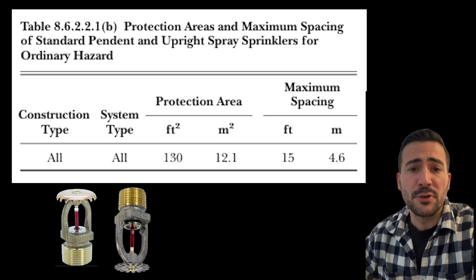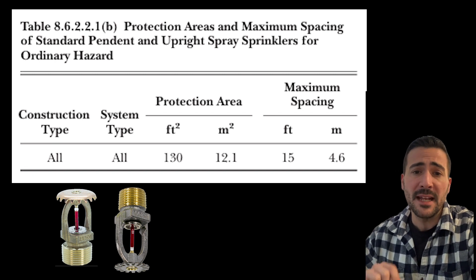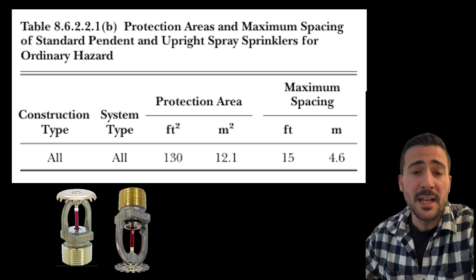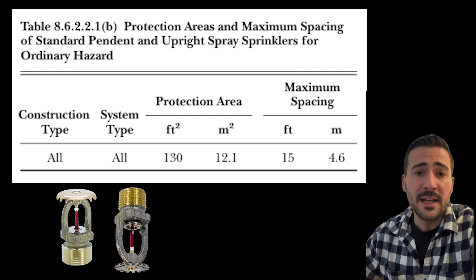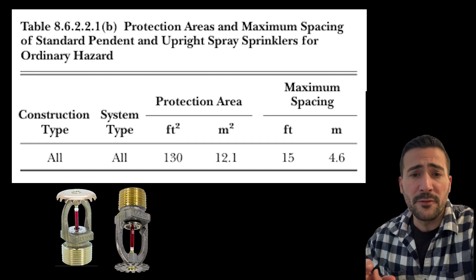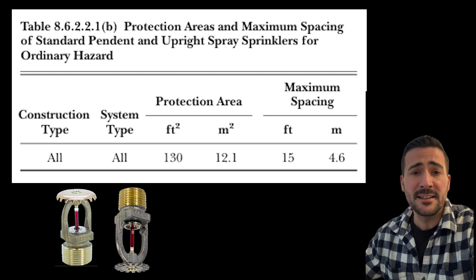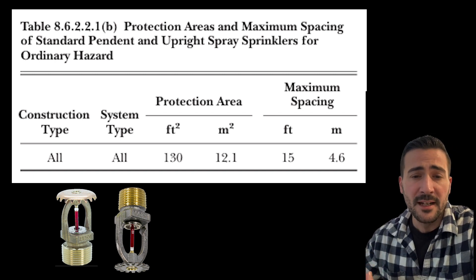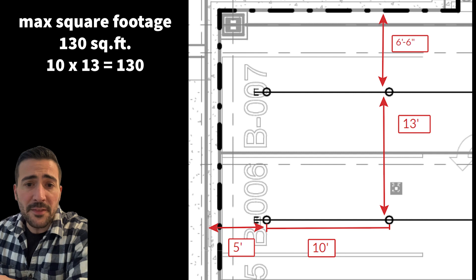Let's start off by going over our maximum protection area of coverage. NFPA 13 made tables for each style head that can be used in ordinary hazard occupancy. These tables give us our maximum square footage and our max distancing for heads. Let's start off by going over the most commonly used head: the standard spray upright and pendant.